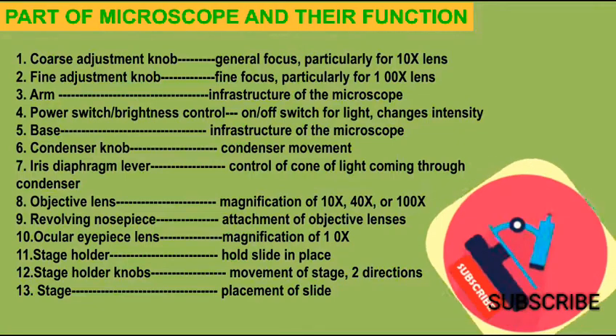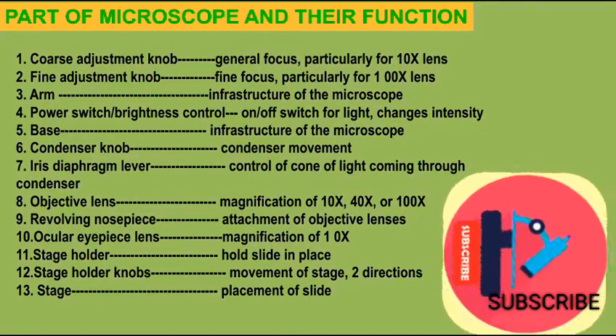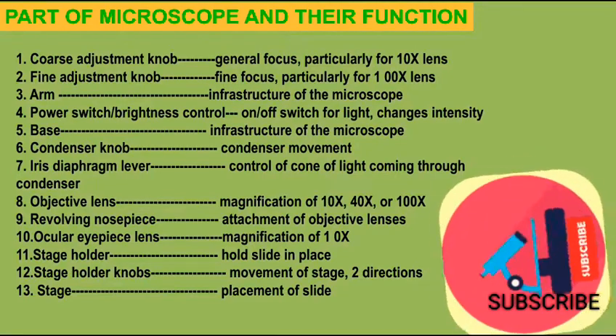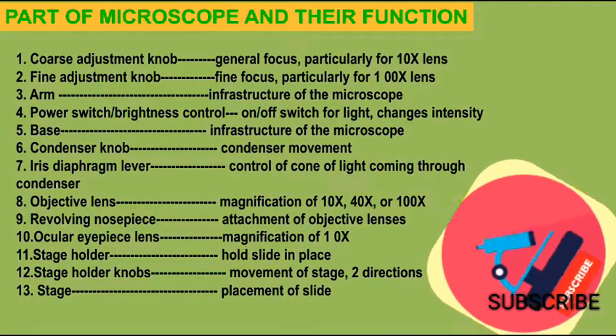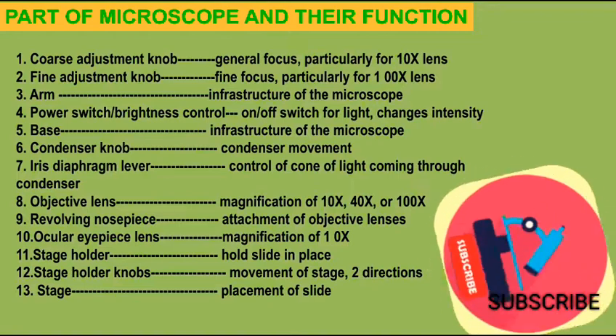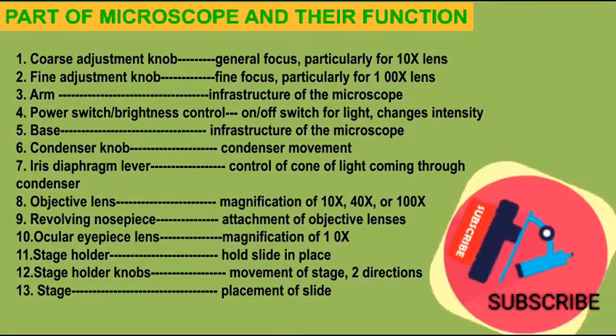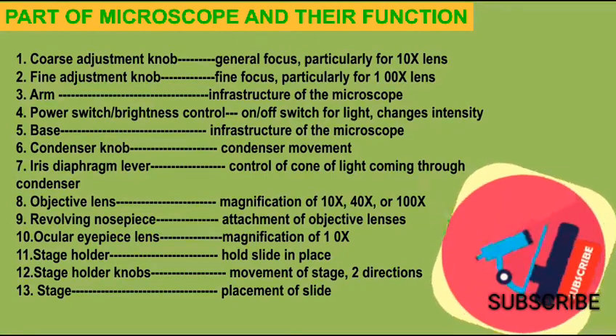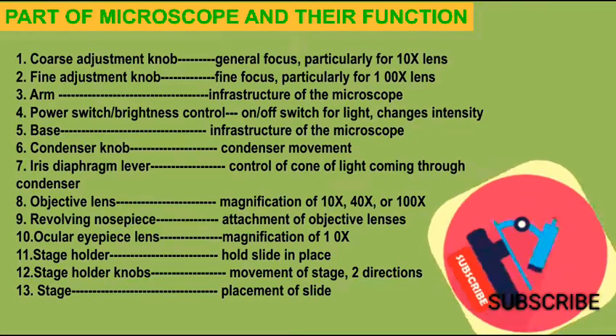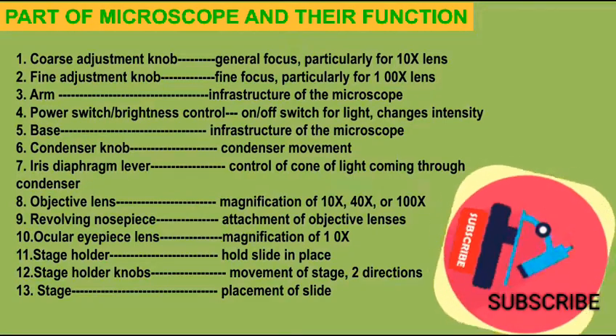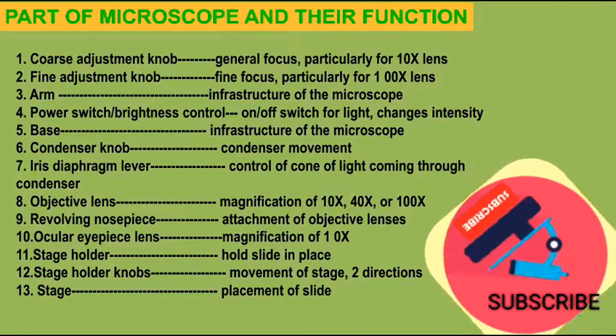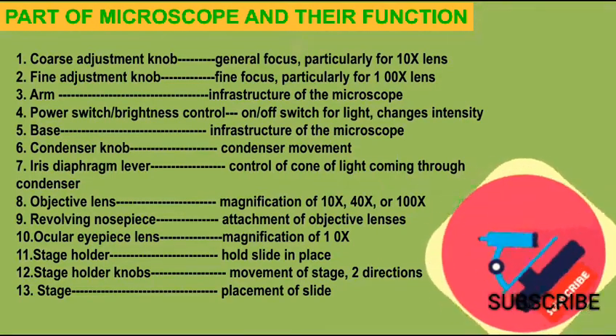Various parts and their functions: the coarse adjustment knob is used for general focusing, particularly for the 10x lens. The fine adjustment knob is for fine focusing, particularly for the 100x lens. The arm is the infrastructure of the microscope. The power switch or brightness control is the on/off switch for light and changes intensity. The base is the infrastructure. The condenser knob controls condenser movement. The iris diaphragm lever controls the cone of light coming through the condenser. Objective lenses provide magnification of 10x, 40x, 100x, etc. The revolving nosepiece is for attachment of objective lenses. The ocular eyepiece lens provides magnification of 10x. The stage holder holds slides in place. Stage holder knobs move the stage in two directions. The stage is the placement area for slides.